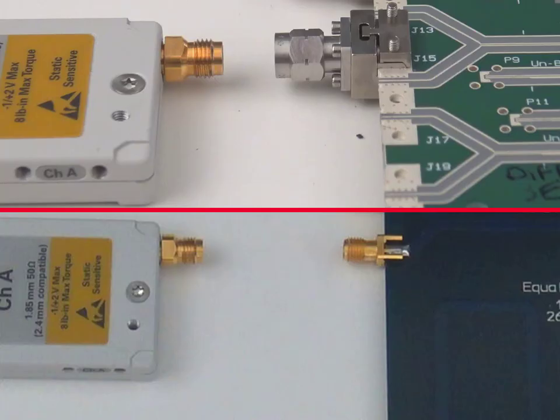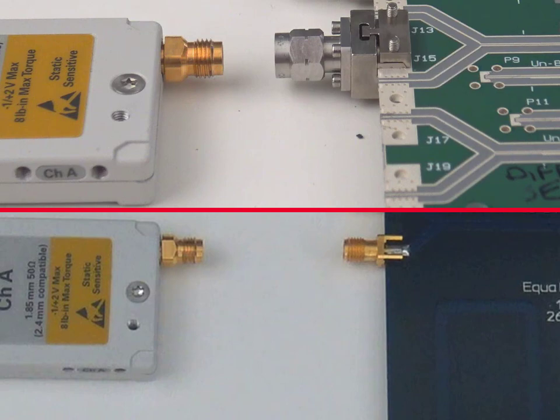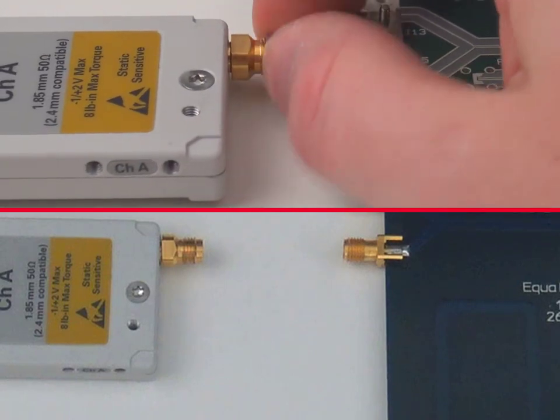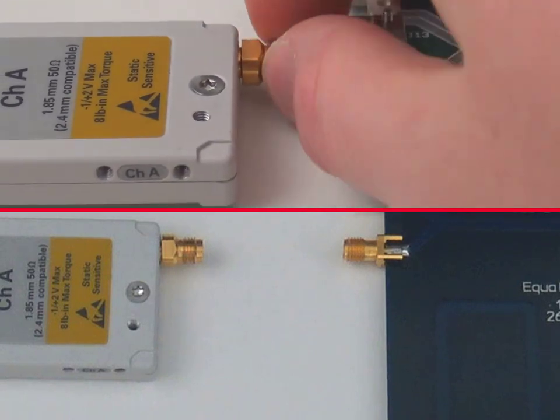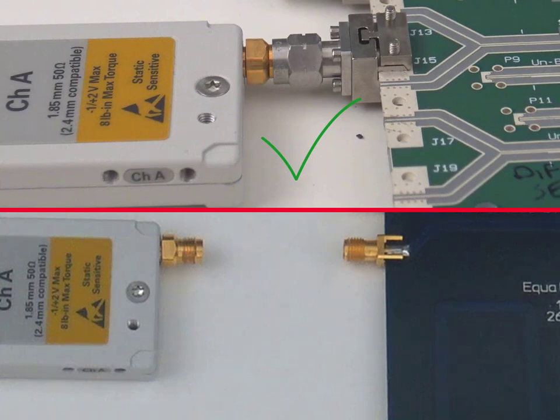The first step to take when calibrating TDR heads is to determine whether or not your measurement head is compatible with your DUT. If your measurement head connects up to your DUT, great! Then all you need to do is hook it up to the eCal and calibrate.